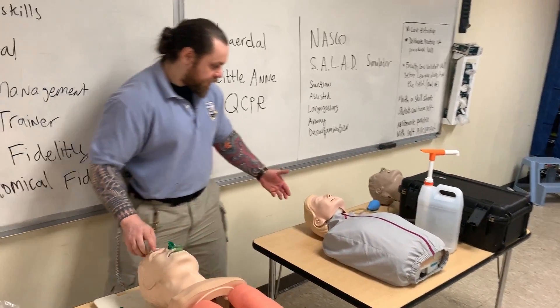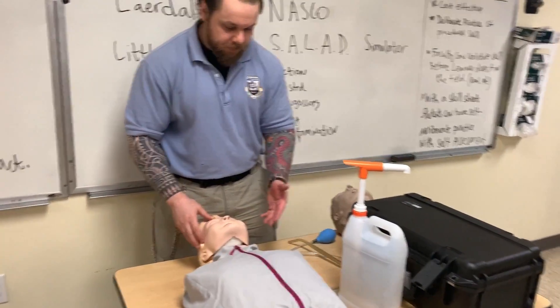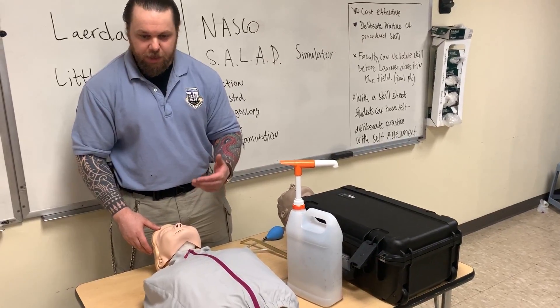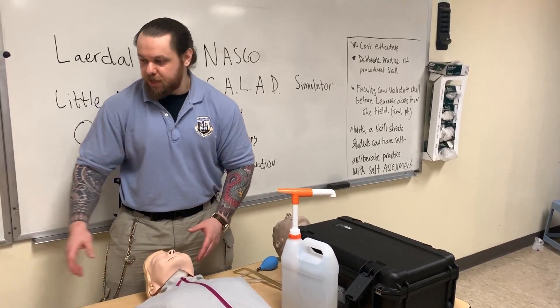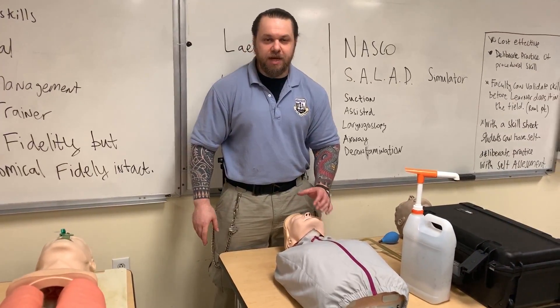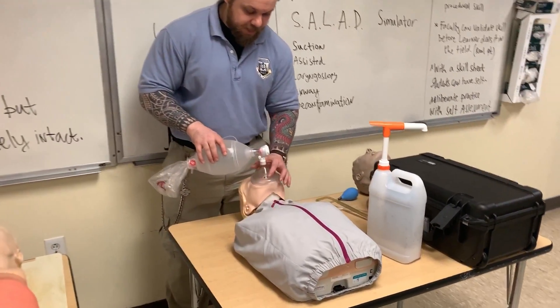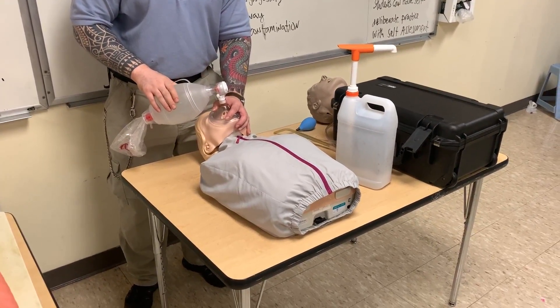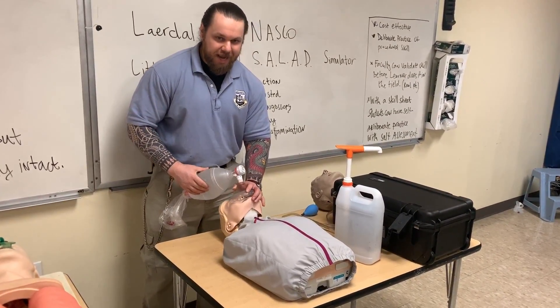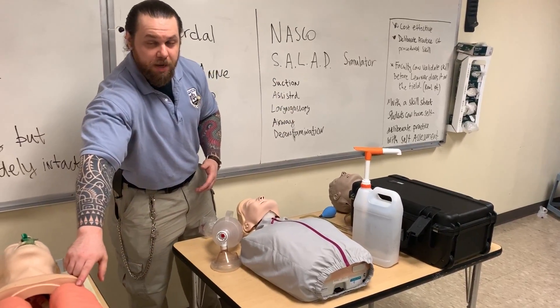If we move to my left, we have two other mannequins. This is Laerdal Little Anne, QCPR trainer. What I noticed is that if students went through an airway station prior to CPR and used this mannequin the entire time, they never learned to do the head tilt. So when they're learning CPR, they're placing the mask and unable to get chest rise. We have to correct them to do head tilt chin lift — they don't build that mind-muscle connection because they get chest rise no matter what on this mannequin.